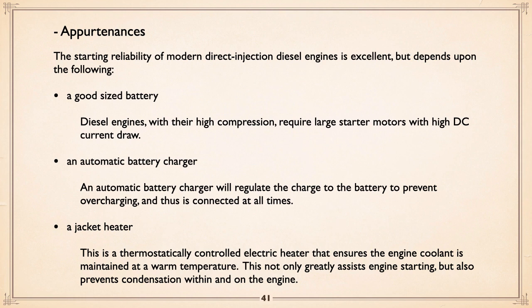A jacket heater. Diesel engines do not like to start cold. So what you do is have a thermostatically controlled electric heater that ensures the engine coolant is maintained at a warm temperature. Not only does it greatly assist engine starting, realize the piston comes up on the diesel, the air is compressed, fuel is injected in. It's the temperature from compression and that high pressure that allows the fuel to combust on its own, no spark plug. So the warmer the engine is, the better it's starting on the first turn. Okay. Also, having this electric heater will cut down on condensation within the engine and around the engine.